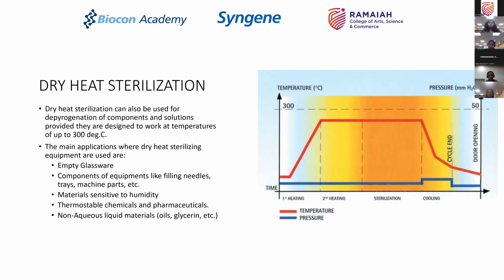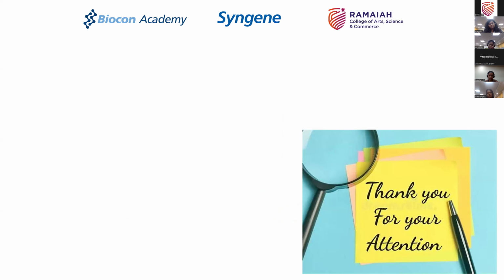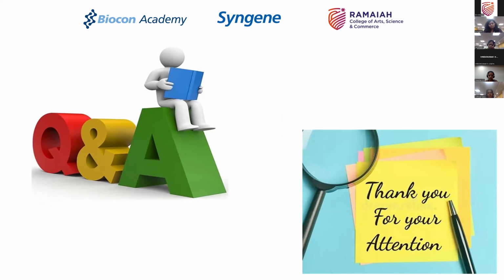So a lot of materials can be dry heat sterilized, as long as they can withstand the heat. With this, on depyrogenation, since we had already done it in the previous class and covered a lot, there are no new factors except the FH value, which is more elaborately expressed here. Of course, that formula was also available in the previous slides.